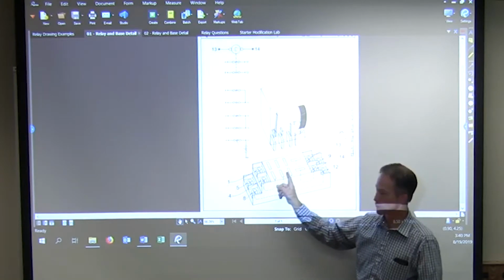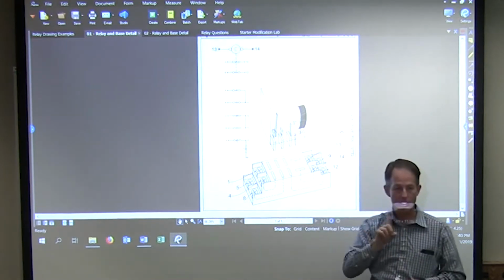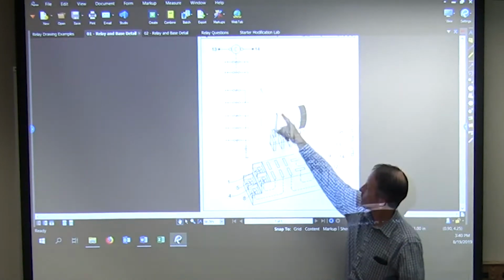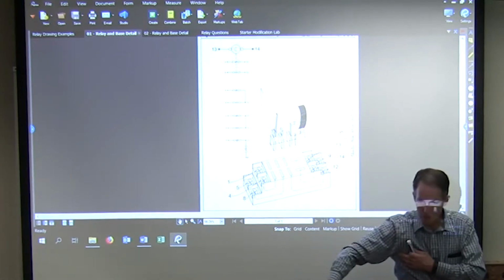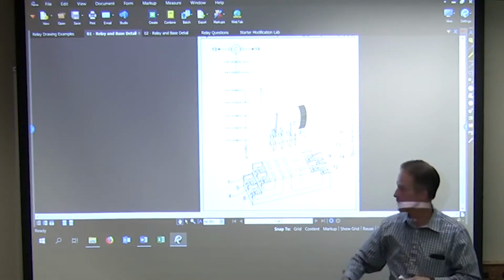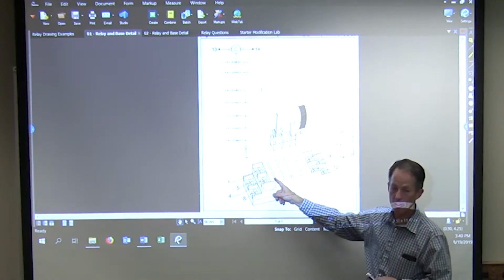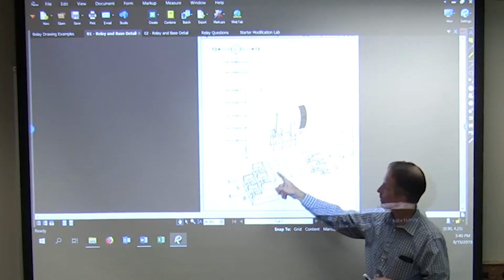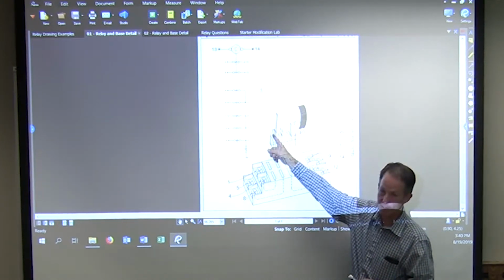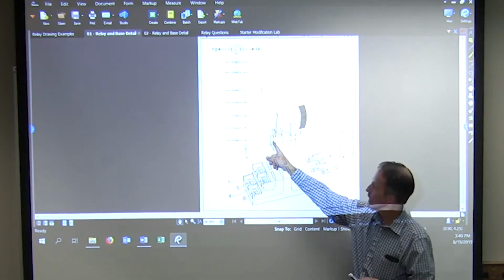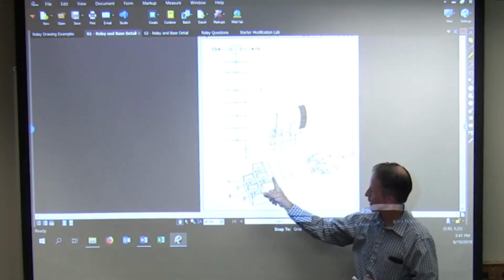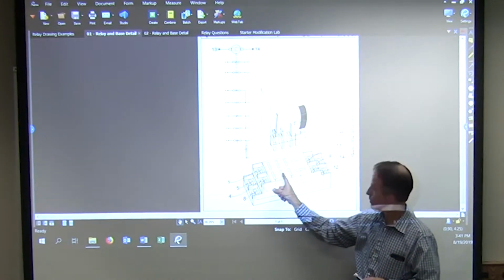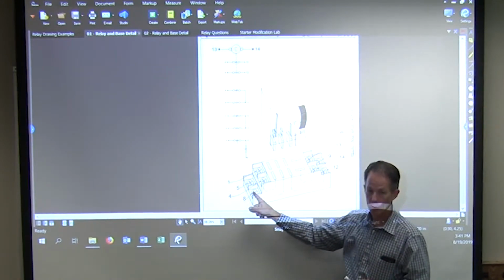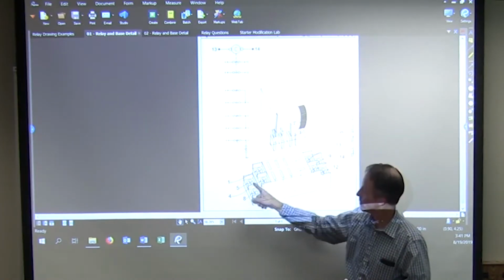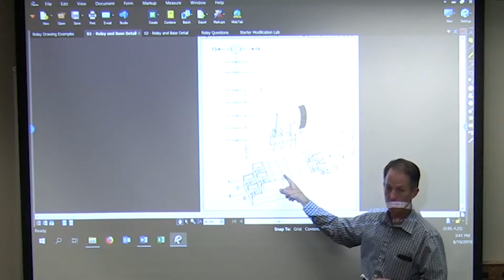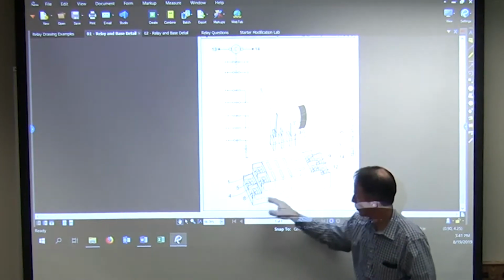So we have these three tabs, which tie into here, as one set of contacts. I have a normally closed. You can see this is a wiper, and it essentially swings from one side to the other as that coil is energized. So this outside is going to be normally open or closed? Closed. Does everybody see that? It's normally closed, because it sits there and the wiper is touching that outside contact. As soon as I energize it, it will pull the wiper from this outside to the one that's closer. So that would be our normally open. So normally closed are the top set here, with the common in the middle, 12 to 4. Okay. Normally closed, and then normally open down here.